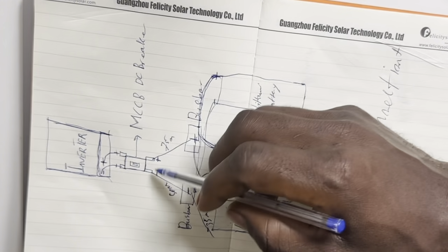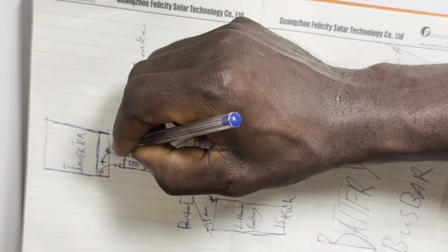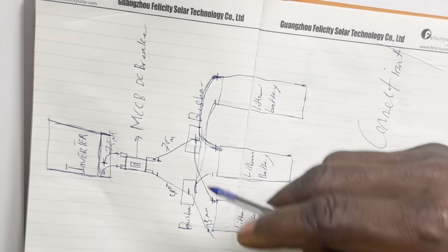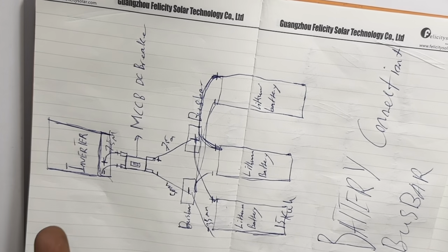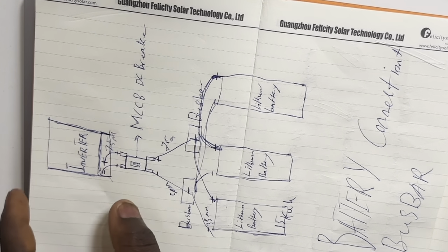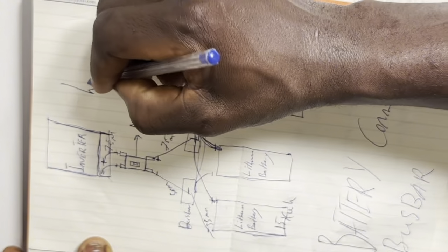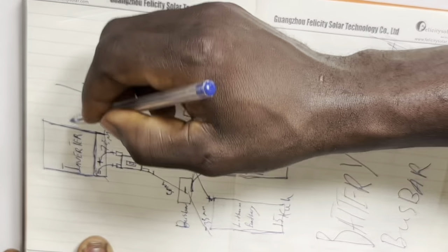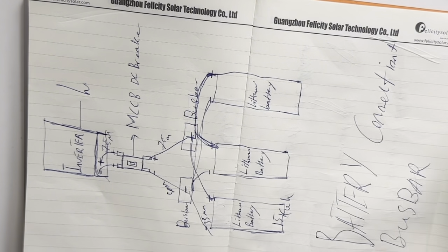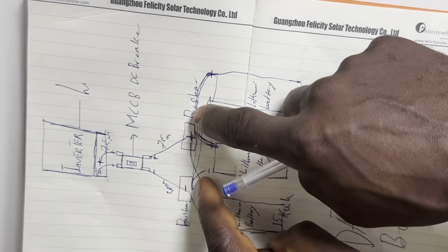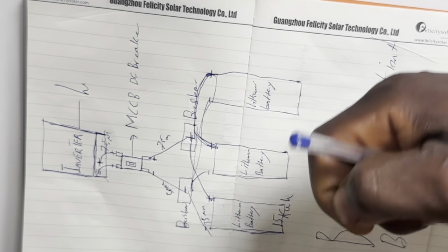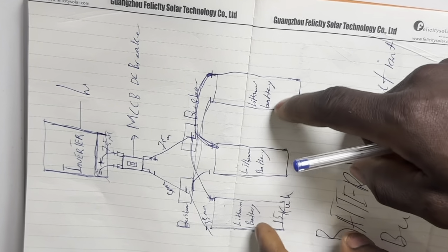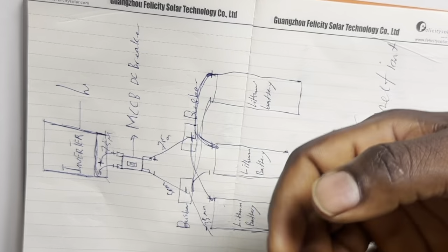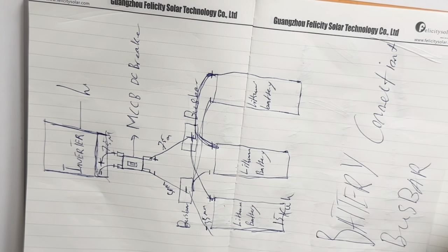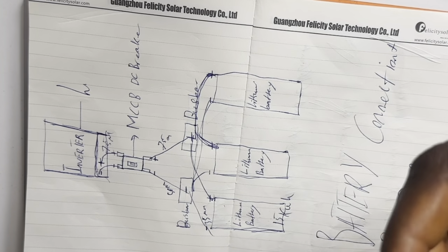So if you use 75 for this one, you have to use the same 75 for the one going to the inverter. The main reason is that most hybrid inverters we use now come with higher charging capacity. If you send current to this bus bar with the same cable capacity used for your lithium ion battery, those cables will likely be overstressed, which can lead to fire outbreak or the cable overheating.